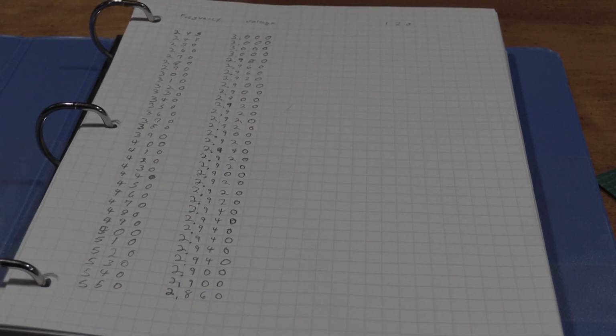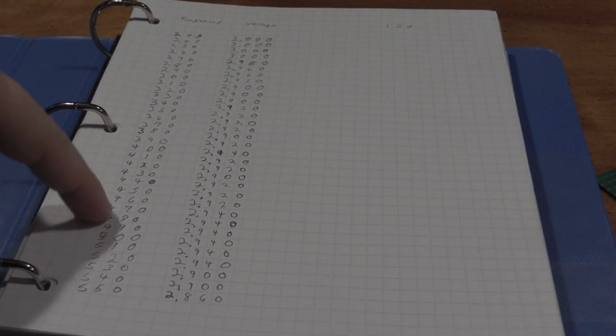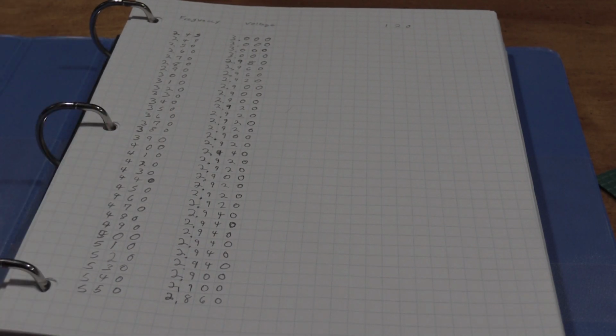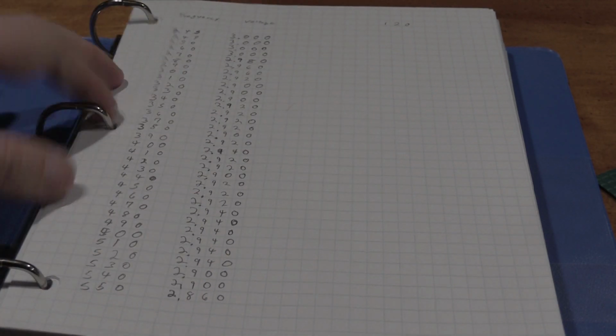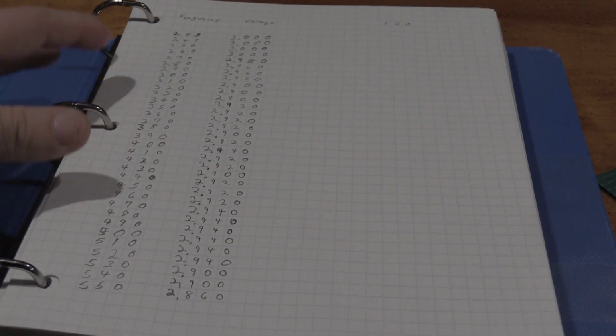So I checked every 10 kilohertz, and the specification on the SG502 is 4% of set point at 50 kilohertz. So wherever you set the amplitude at 50 kilohertz, 4% deviation from that. I had it set at 2.8, so we jumped up a little bit, but then it came back down. So everything was good. This hits 4% just barely, but we are within spec, so everything is good to go.